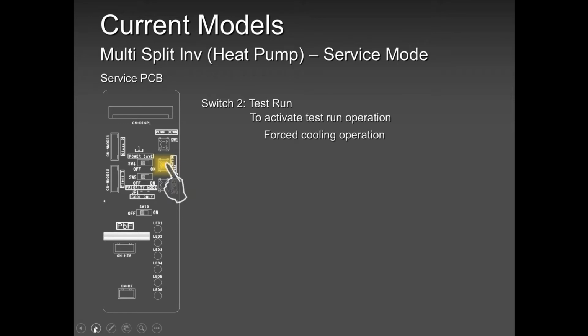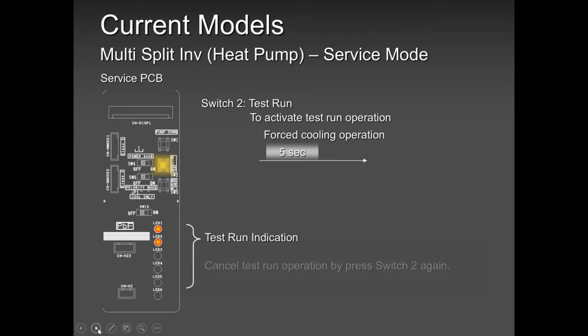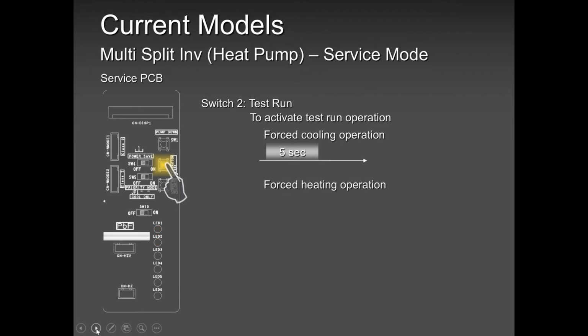So when you press the test run, the unit goes into forced cooling. You will see the 2 lights, the LED 1 and 2, are on. That means you are in test run cooling. If you keep pressing this test run button, the number 2 will go off, number 3 will come on. Okay, that means you are in forced heating. You see the number 2 light went off because you kept holding. So now you are in test run heating.